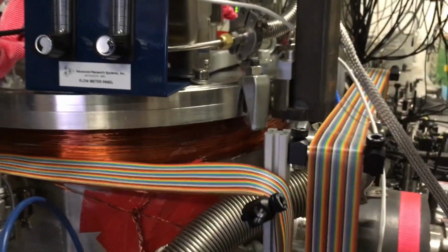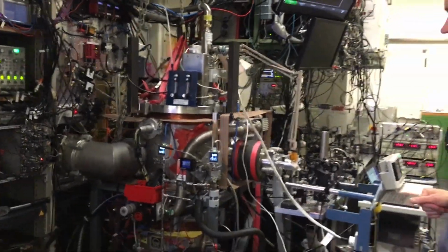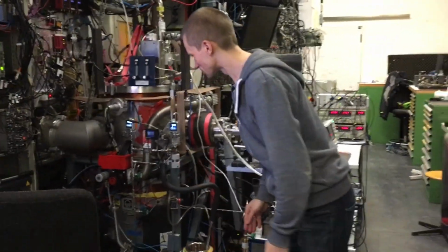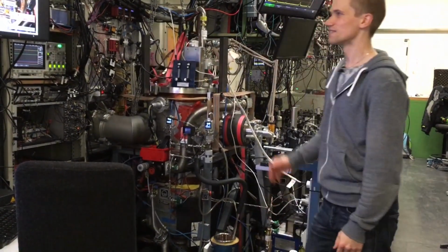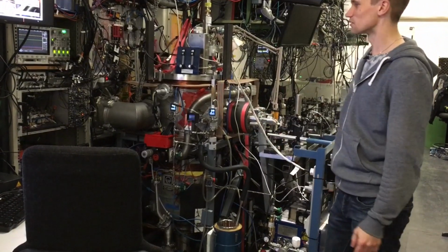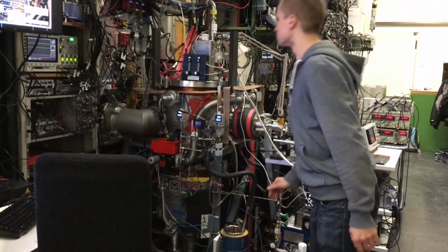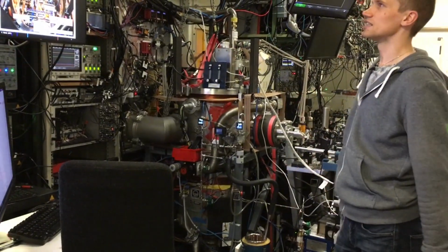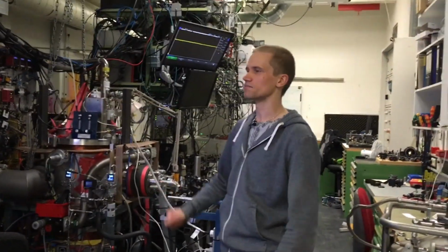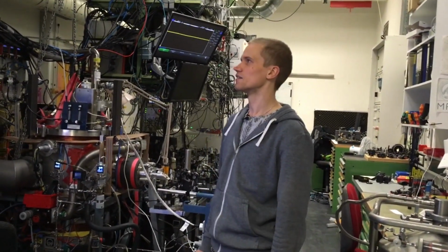And why is the chamber so big in size, I mean vertically? This is because we have the cryo pump on the bottom. If I switch it on, you see that it begins to cryo pump the whole region. Through this cryo pump, we achieve a pressure of a few times 10 to the minus 8 millibar.